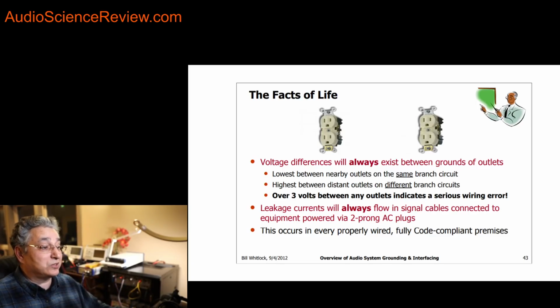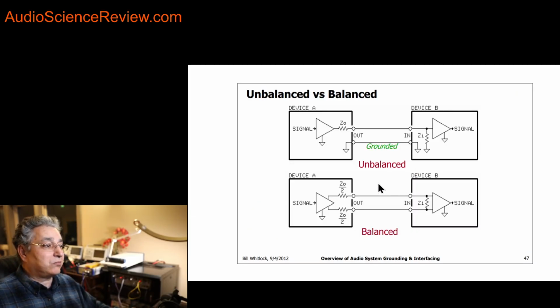Up to 3 volts can be allowed, and I've got a special meter you can get that'll show you the voltage drop differential between these outlets. So remember, even in a fully code compliant premise, you can still have a differential between these outlets. So what does that mean, that I have this differential?